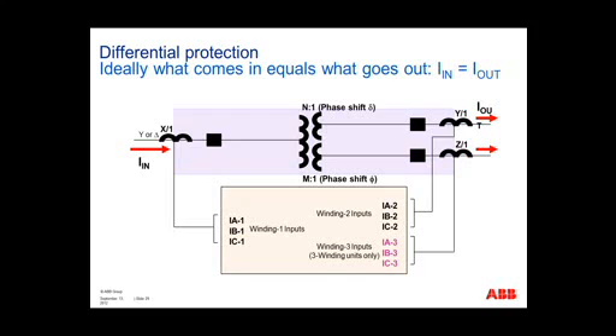The basics of differential protection, which is similar to your bus bar protection, is if we assume load flow from left to right, we can see that the current going in should equal the current leaving the low voltage winding and the tertiary winding. And this current is multiplied. The difference between the transformer and bus is that there is a turns ratio that has to be accounted for. So the ampere balance equation is the current going in times the turns ratio equals the current leaving.